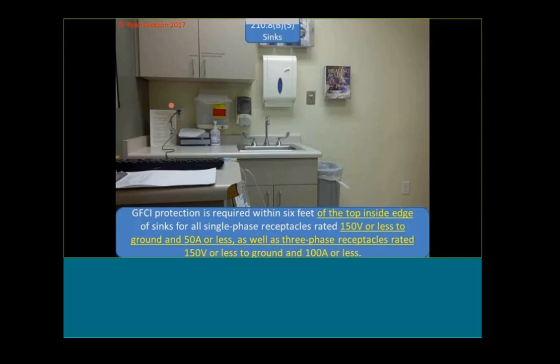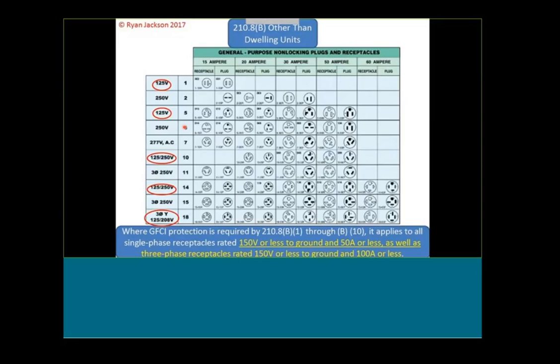See this receptacle right here with the buttons? That's what we're talking about. Let's talk about a change you'll need to be aware of—this is for commercial, not for houses. Down here at the bottom, GFCI protection is required by 210.8B1 through B10, which covers outdoors, kitchens, near sinks, and things like that.